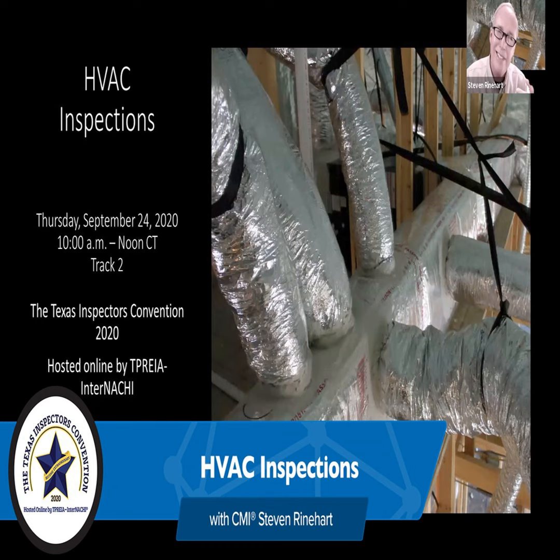I don't think I saw where you can't touch. I've heard people say that when they touch, there's a condensation potential. It's probably more in older ducts that just had R4.2. I don't know where they got that R value. The issue comes around condensation, sweating like a glass of iced tea. You run cold air in there, you've got a hot, humid attic, you can condense on the outside.